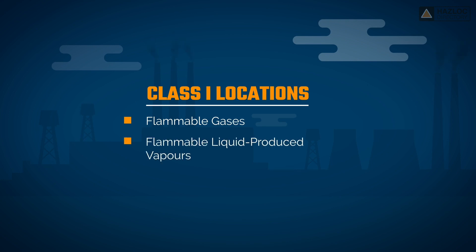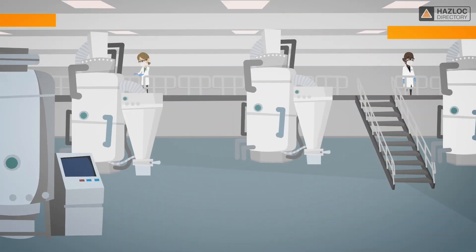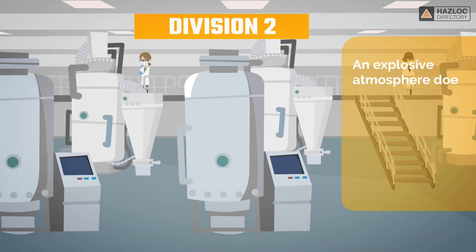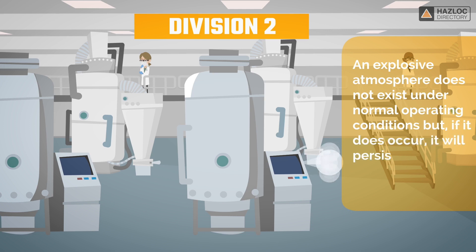Class 1 means that the location contains flammable gases, flammable liquid-produced vapors, or combustible liquid-produced vapors. Division 2 means a location where an explosive atmosphere does not exist under normal operating conditions, but if it does occur, it will persist for a short period only.